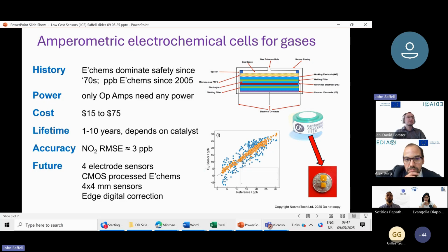You don't get both. And the cost for sensors is $15 to $75. In volumes, they tend to be around $30 to $40 each. Lifetime is 1 to 10 years, and the lifetime doesn't depend on the manufacturer. It depends on the catalyst they're using. The noble metals like platinum last a long time, and some of the catalysts like the carbons don't last as long. So the lifetime really depends on the type of sensor, and any manufacturer saying all their sensors have the same lifetime is incorrect.